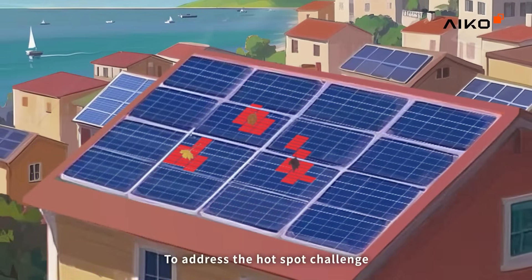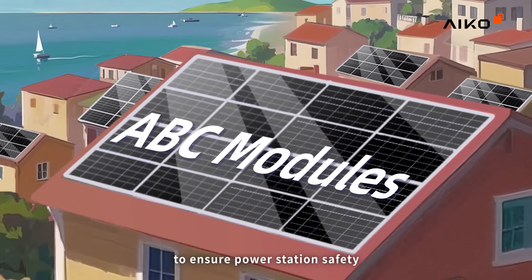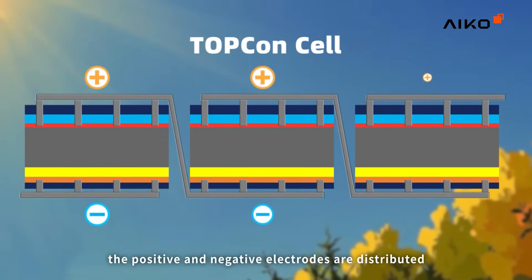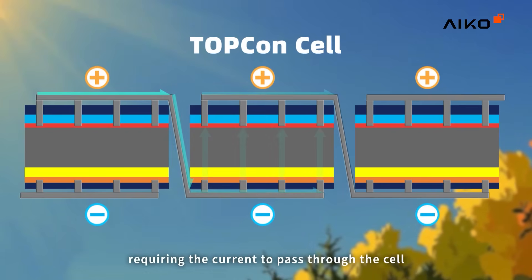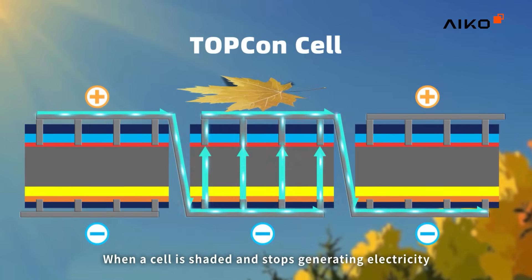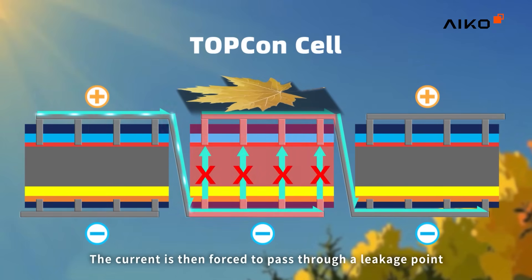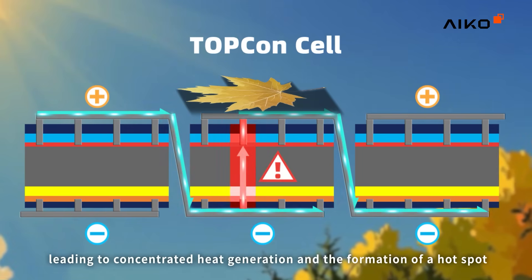To address the hotspot challenge, AIKO has introduced a revolutionary solution to ensure power station safety. In traditional modules, the positive and negative electrodes are distributed on both the front and rear of the cell, requiring the current to pass through the cell. When a cell is shaded and stops generating electricity, it turns into a high resistance. The current is then forced to pass through a leakage point, leading to concentrated heat generation and the formation of a hotspot.